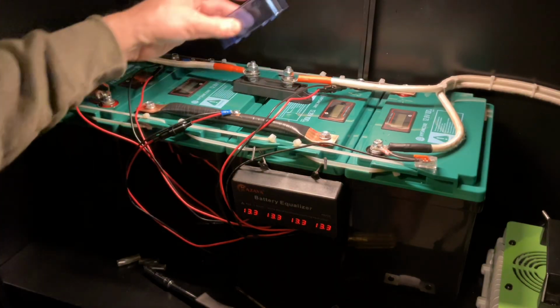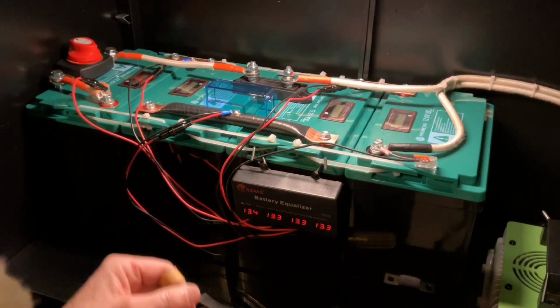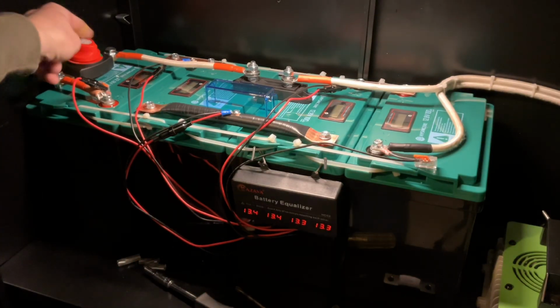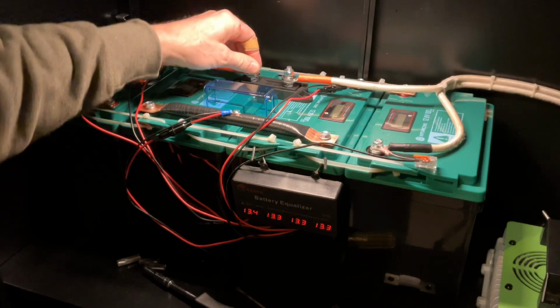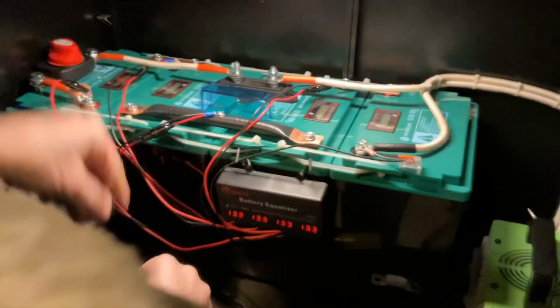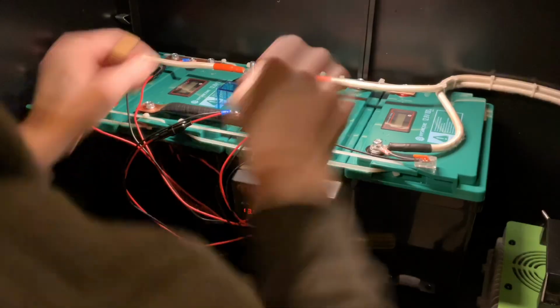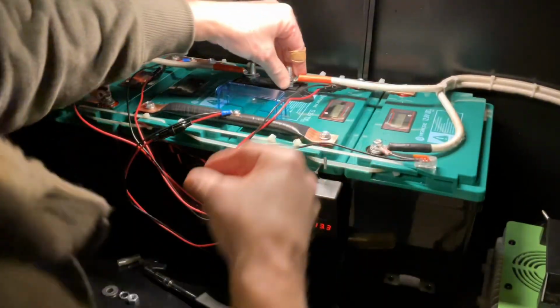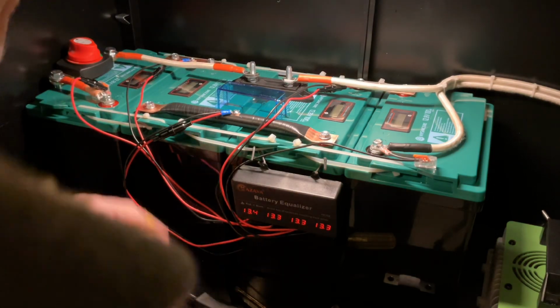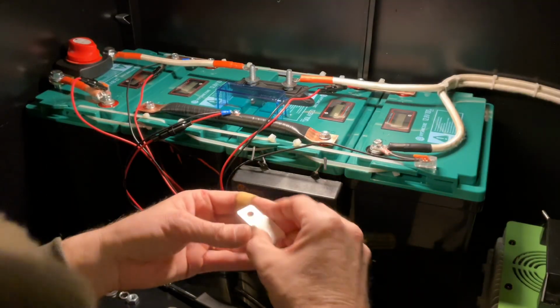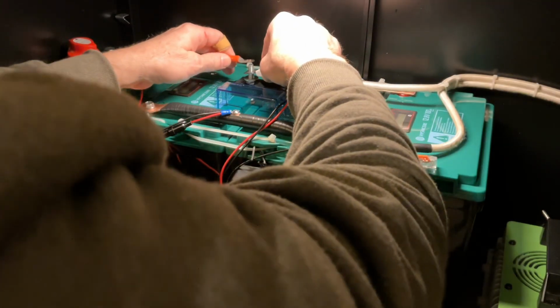I still do have the fuse removed from the system, and the battery disconnect is turned off, so we can go ahead and put our fuse back in. With this new fuse holder location, not directly next to the main positive and negative connection on the 48-volt pack, it provides a little bit more safety while working around it. Got a 150 amp Victron fuse.